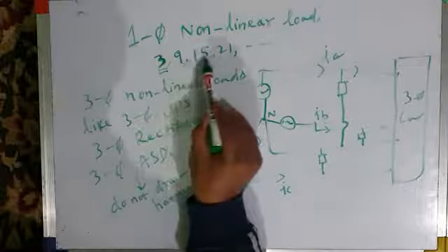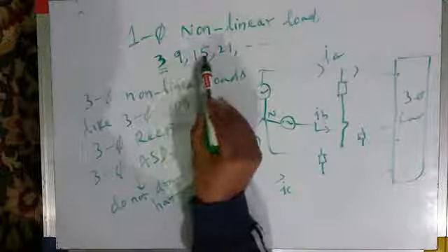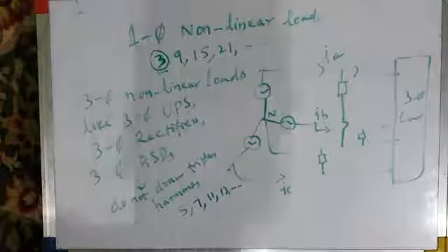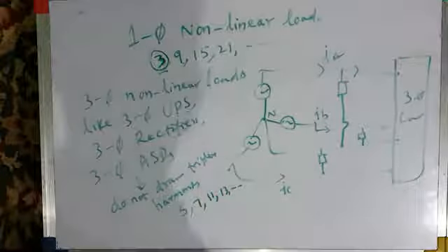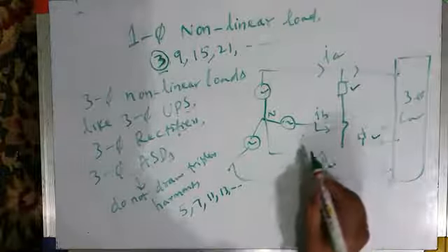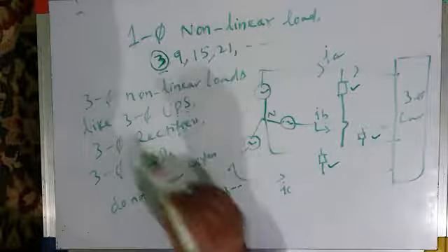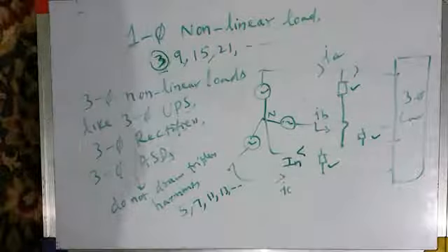In addition to non-triplen harmonics, they also draw triplen harmonics, like the third, ninth, 15th, 21st, and so on. And they draw a very strong third harmonic and triplen harmonic component of currents. Therefore, it is the single-phase loads placed on a three-phase four-wire system which cause the flow of third and triplen harmonics, and hence they result in the flow of strong neutral currents, IN.